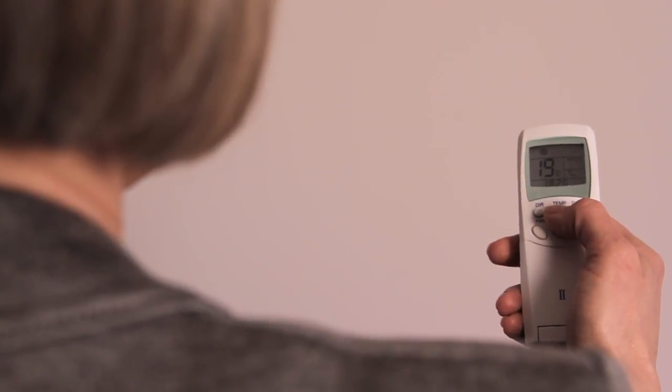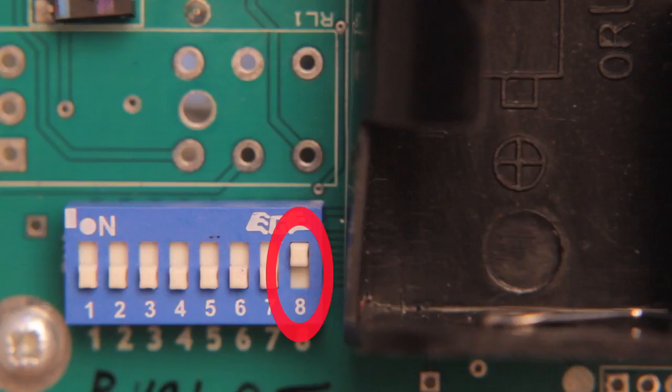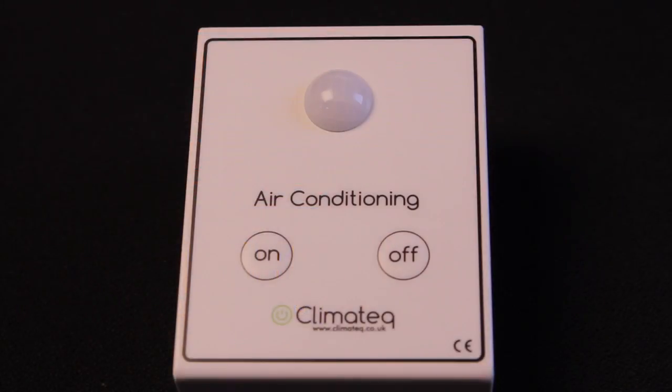Turn the air conditioner on. Set the remote control with the required settings for temperature, heating, cooling, fan speed, and oscillation. Turn the air conditioner off. Set switch 8 to on for test mode. Press and hold the on and off buttons on the pendant together.